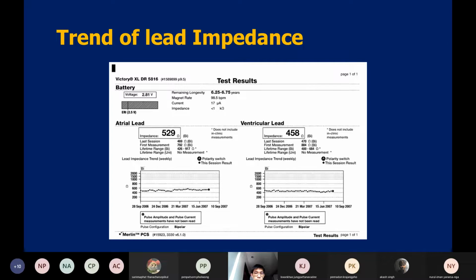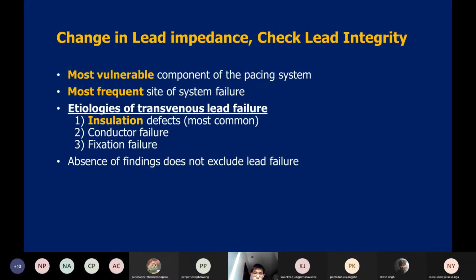You have a trend of the impedance over time, and you can see that if the trend is the same over the automatically checked impedance, the pacemaker would not have any problem. But if the trend has changed a lot from one time to another, you need to consider if there is something wrong with your leads. The lead is the most vulnerable component of the pacing system.